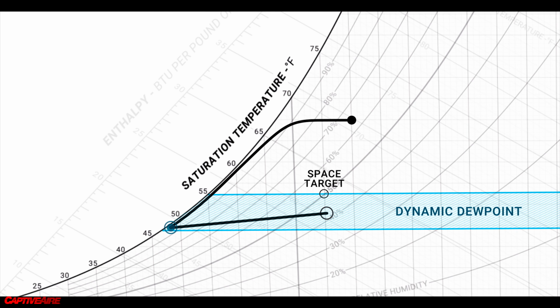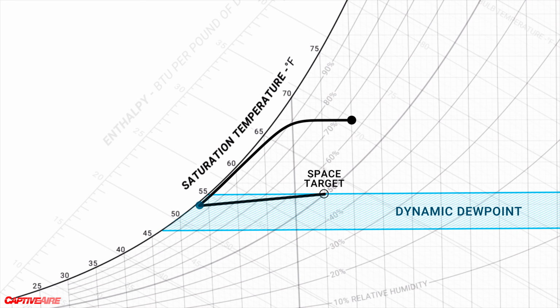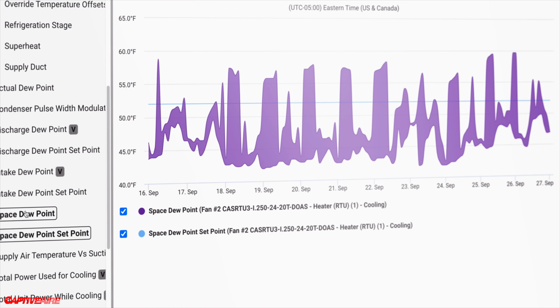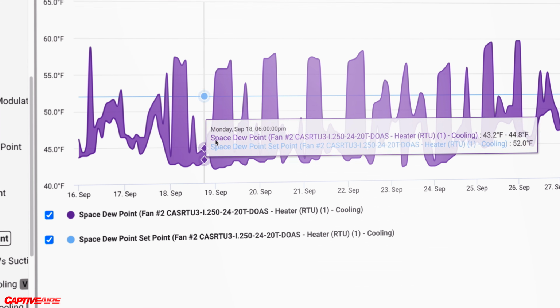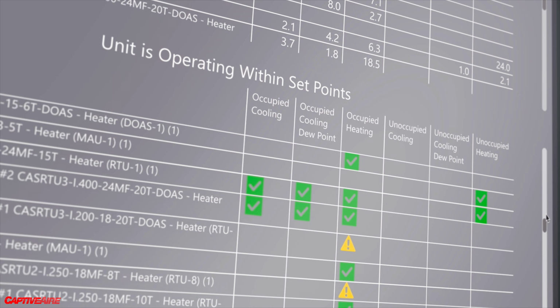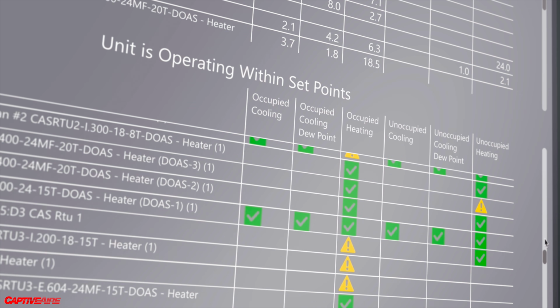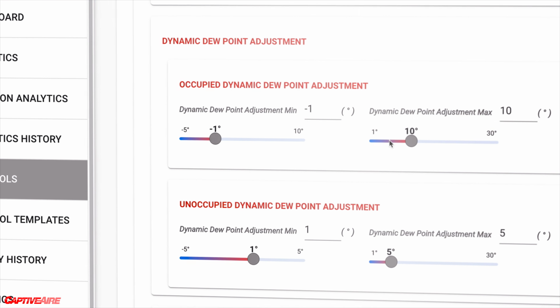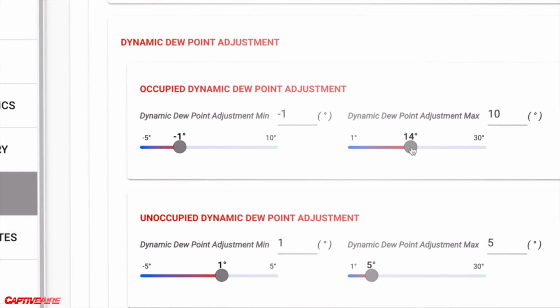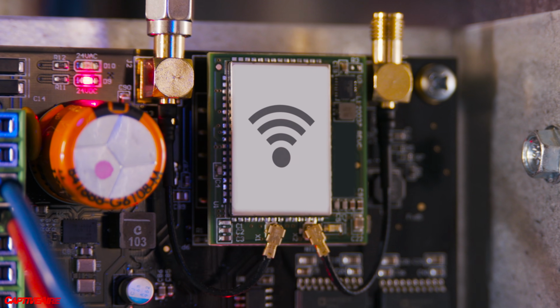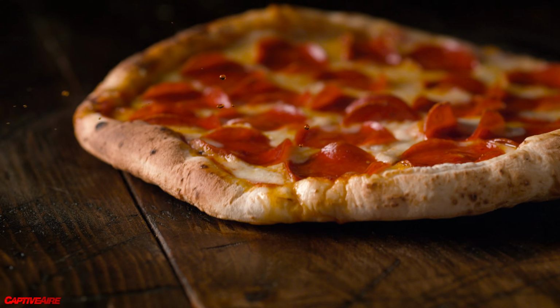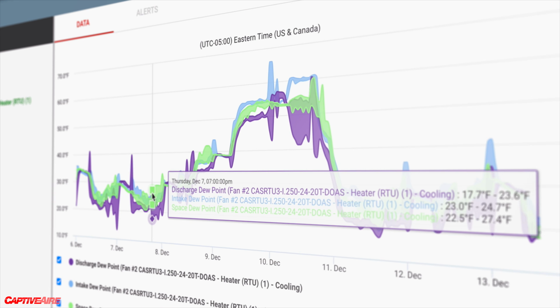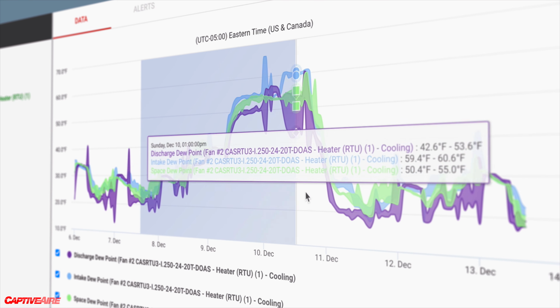The dynamic dewpoint logic we talked about earlier is a perfect example of this. The team found an over-dehumidification trend in multiple units across the country using CASLink data, and it stood out enough to take action and develop this newer logic. Then all we had to do was implement this feature via a simple remote software update. And this is actually what we did with the pizza chain location. That was that exact example. We realized that one of the units wasn't configured with this option, we identified that, and we were able to upgrade the equipment at no cost to help the customer be more efficient.